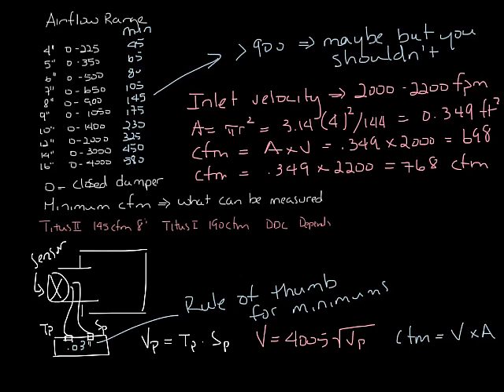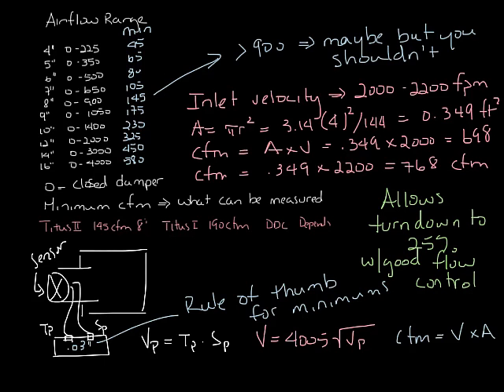And if you select your inlet size so that you're near the 2,000 feet per minute range, you'll also be able to turn your box down to about 25% airflow, or 500 feet per minute, and still be able to maintain proper flow control.